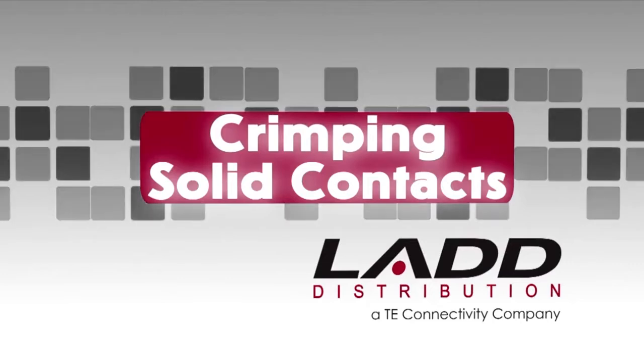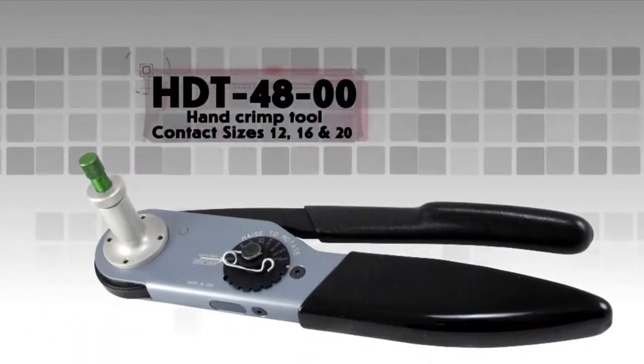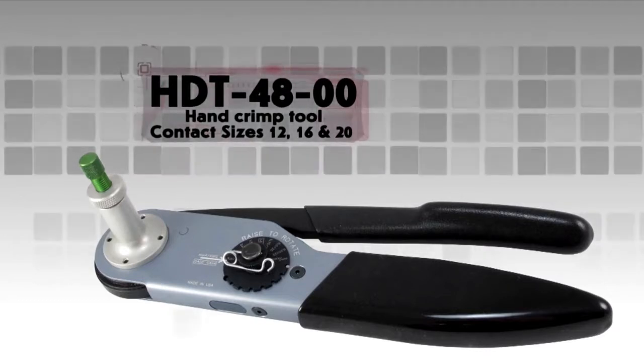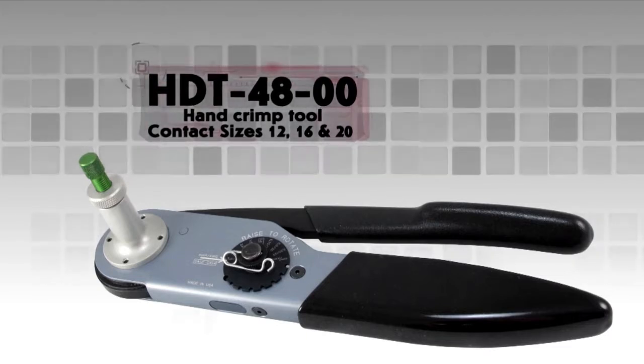Crimping solid contacts using hand tools. For this demonstration, the HDT-48-00 hand crimp tool is being used. This tool will crimp sizes 12, 16, and 20 solid contacts.